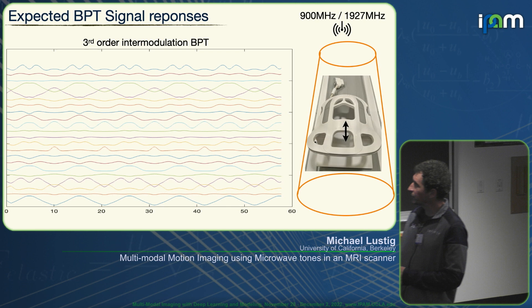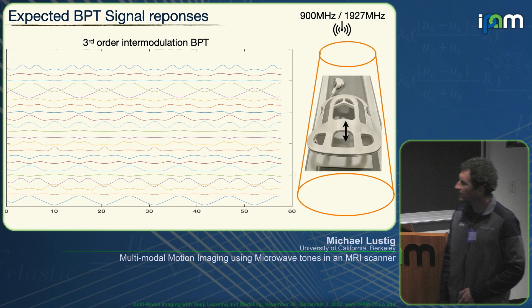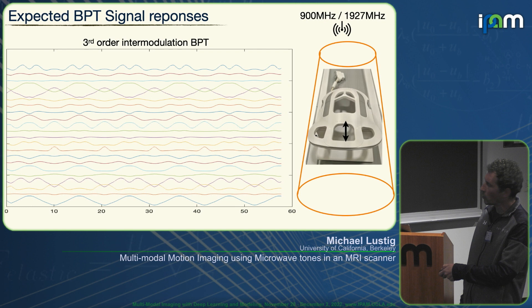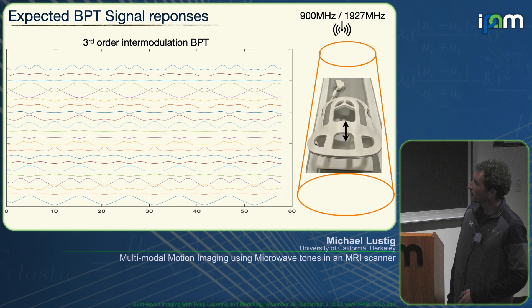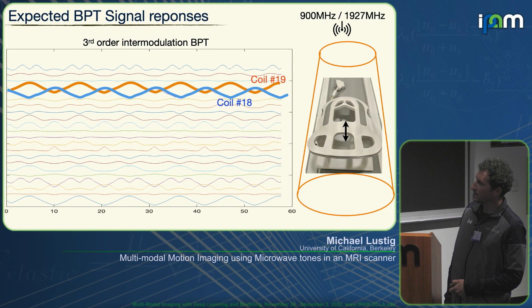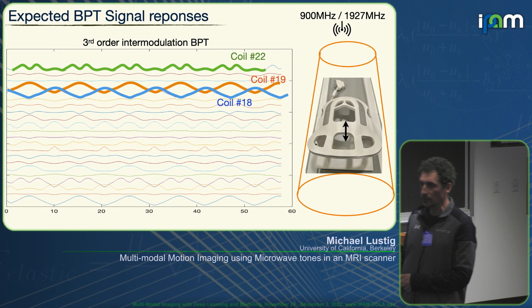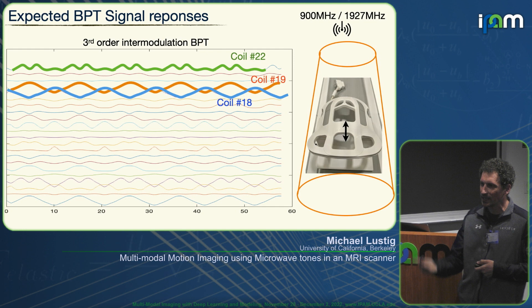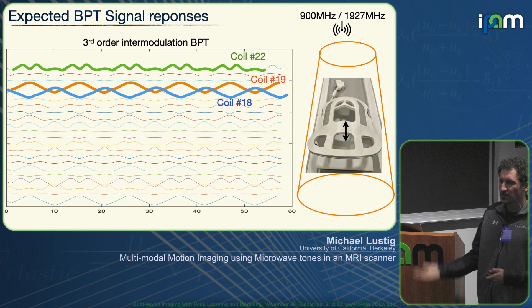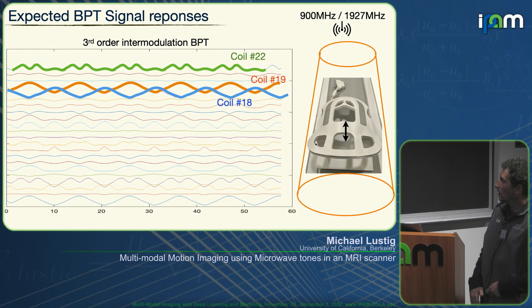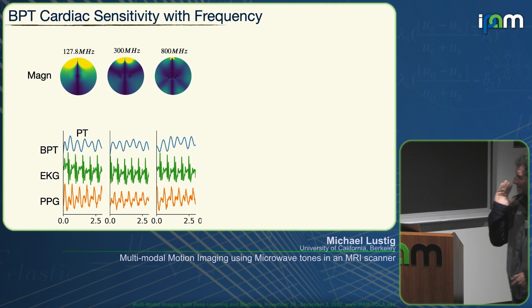We did this experiment with frequencies at 900 megahertz and 1927 megahertz — a third-order intermodulation — with 22 channels being received. We moved a head array inside the bore up and down repeatedly and observed the responses. We saw the expected positive response on some coils, inverted responses on others, and camelback responses on still others, confirming these nulls and troughs are actually appearing — not just in simulation but experimentally. Each coil has a slightly different response depending on its position, which is extremely useful from an information point of view.